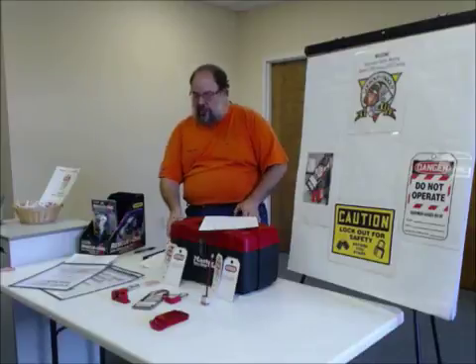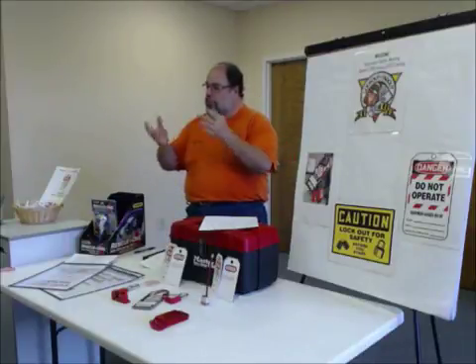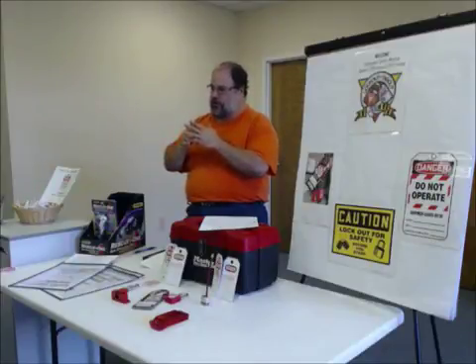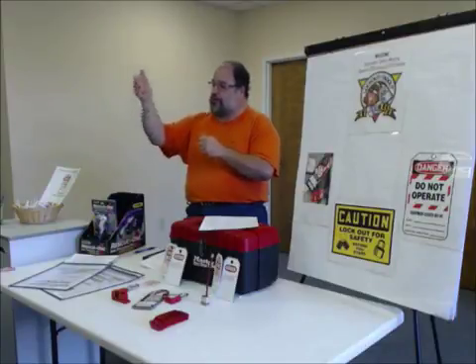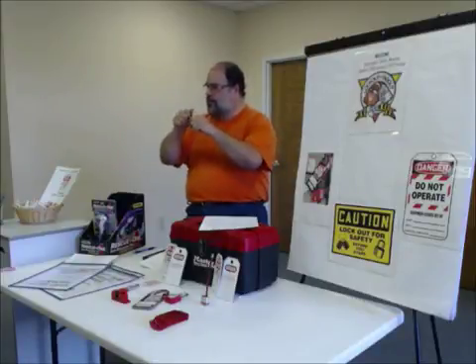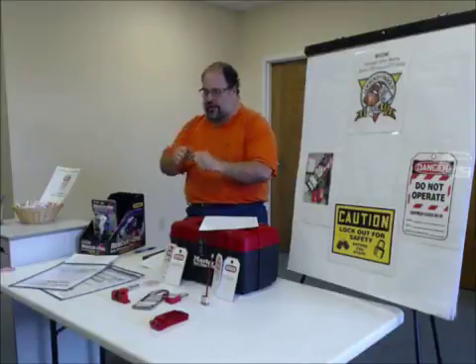It was asked in the last class, a great question. If 2 people are working on a piece of equipment, one of them finishes up, the other one's still locked out, come the end of the shift, that person's going home, but the second shift comes in, they're going to start working on it. What do you do? You just give them your key? No. They have their own lock. They put their lock on before you take your lock off. That way that machine is not unlocked at any point in time when it's not ready to operate.